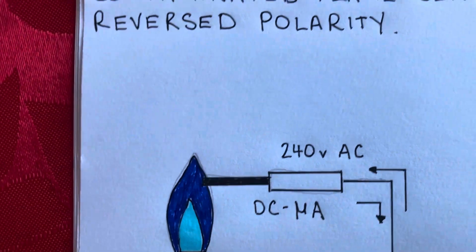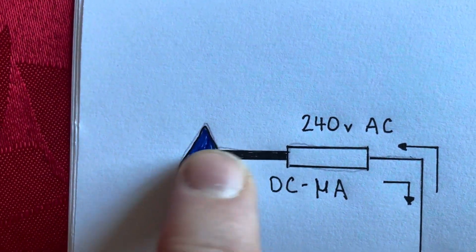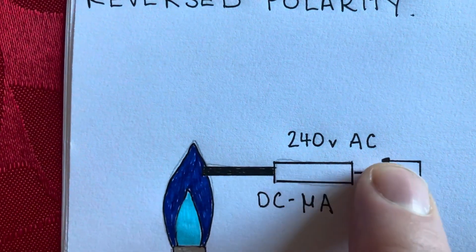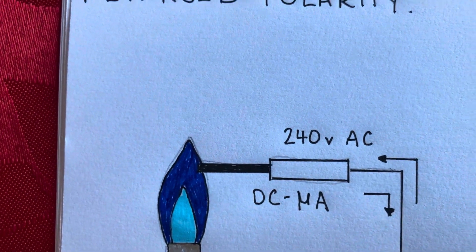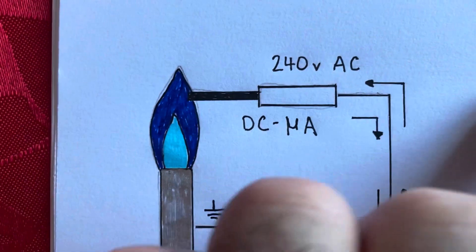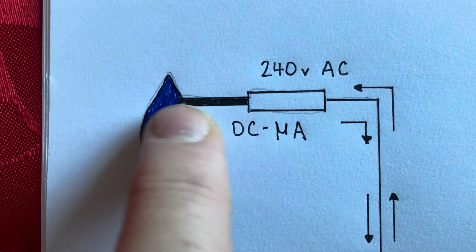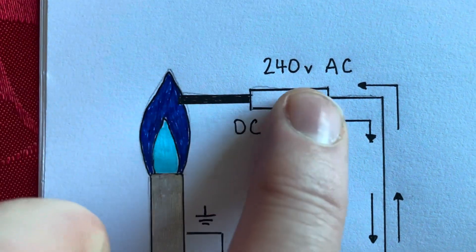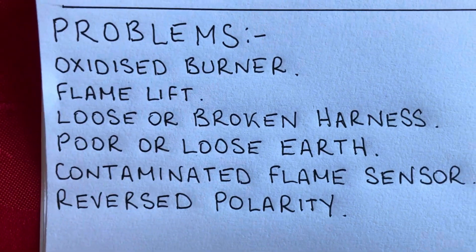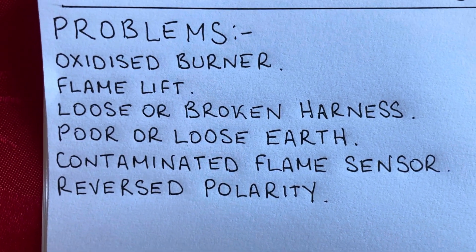A contaminated flame sensor — carbon buildup on it — is another issue. On a service you want to be cleaning that off. Carbon buildup means it can't send a good signal back down to the circuit board. You can test it with your multimeter on ohms and make sure you've got a good connection on your flame sensor.